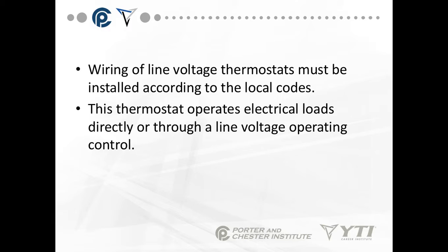The thermostat operates the electrical loads directly or through a line voltage operating control. The electrical code is NFPA 70A or 70, and you have to follow whatever local version it is. All junctions on line voltage have to be inside a metal junction box that's covered.